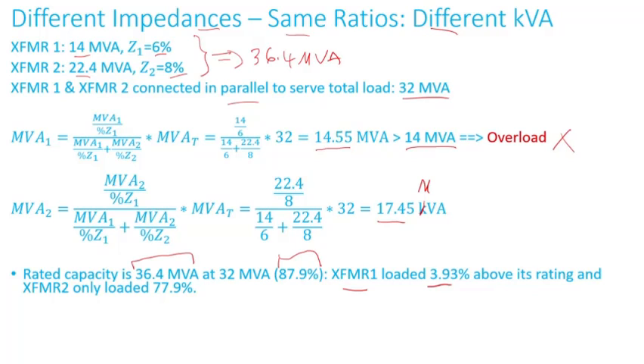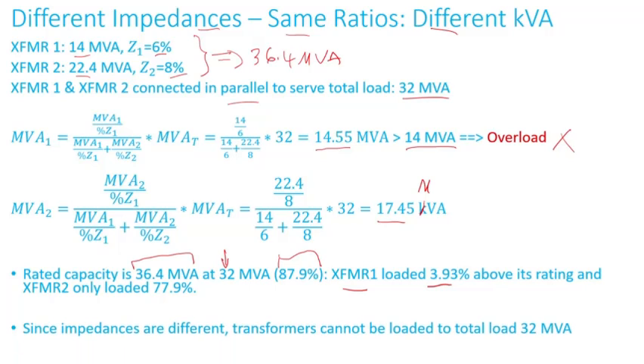In other words, if this load goes up even more, transformer one will be overloaded even more. Since the impedances are different, these transformers cannot be loaded to 32 MVA — otherwise you're going to damage transformer one if it sustains that overload for a long period of time.